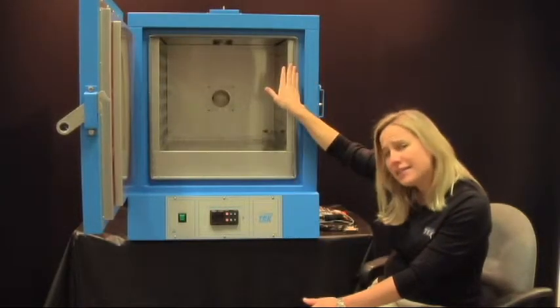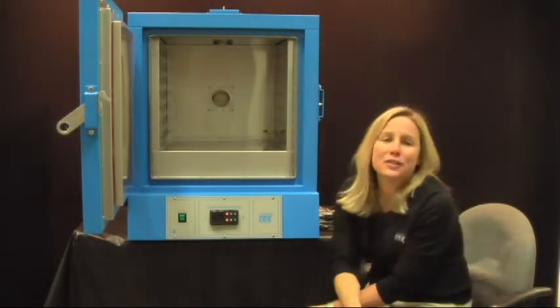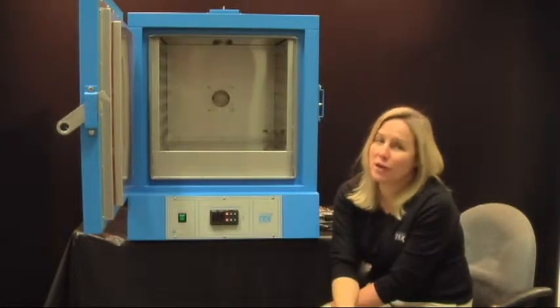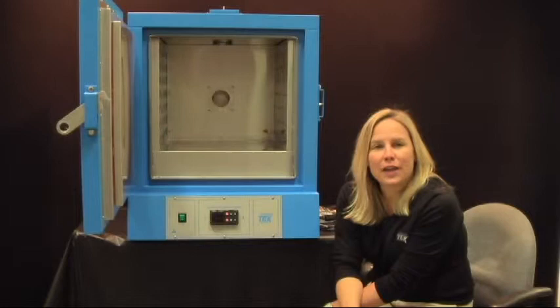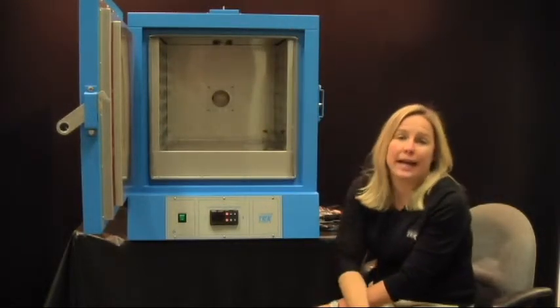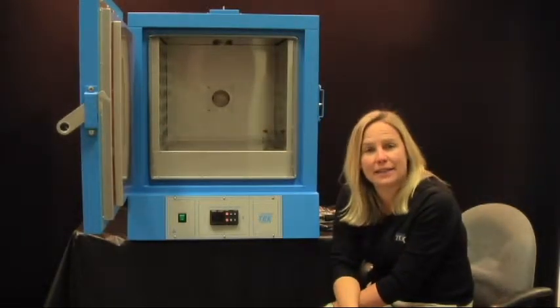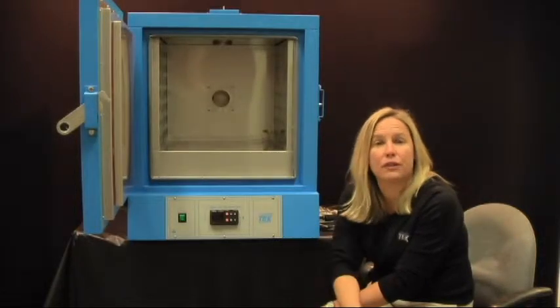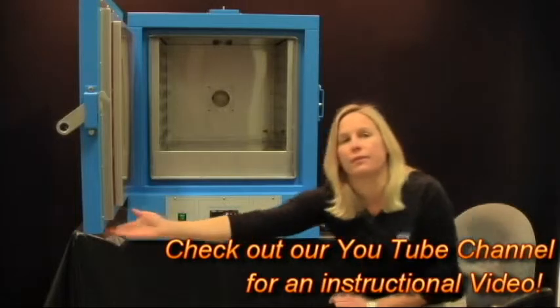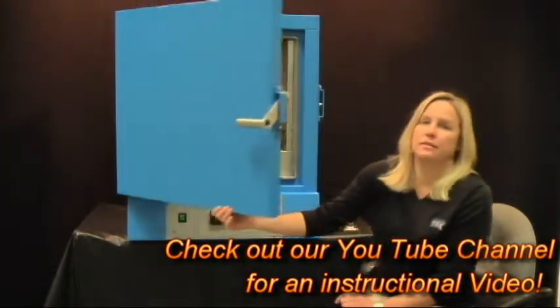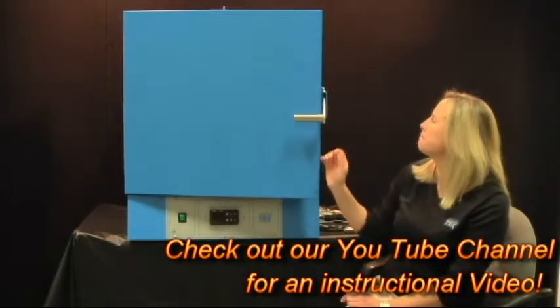If, for some crazy reason, you need to go hotter than 235 degrees C, please let us know and we will change out this gasket to a high, high temp gasket that will be able to achieve the 300 degrees C that we need. Or we could send it to you, you could do it yourself. Yes. Easy field retrofit. Yes. We'll show you how.